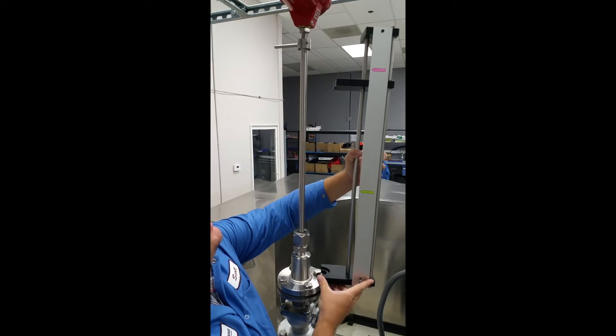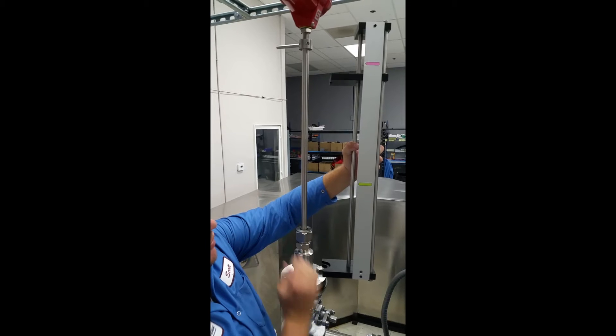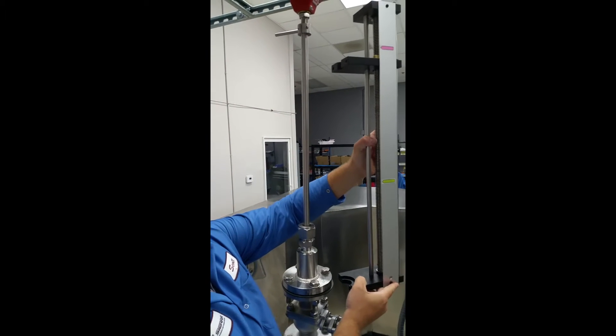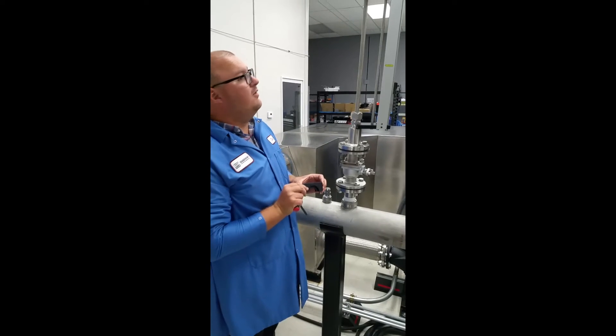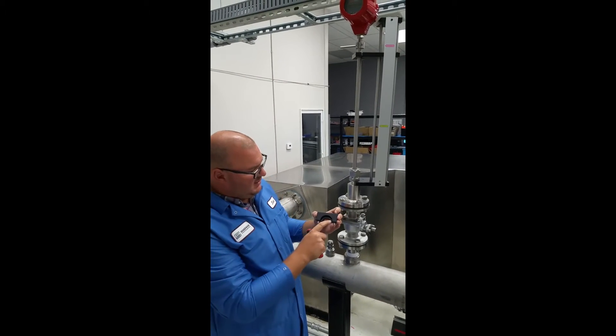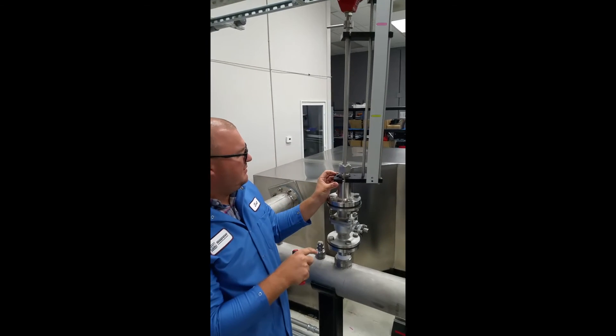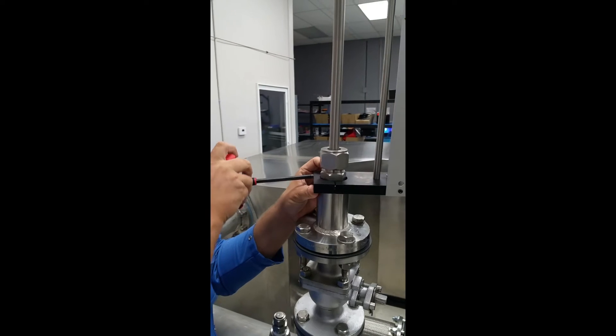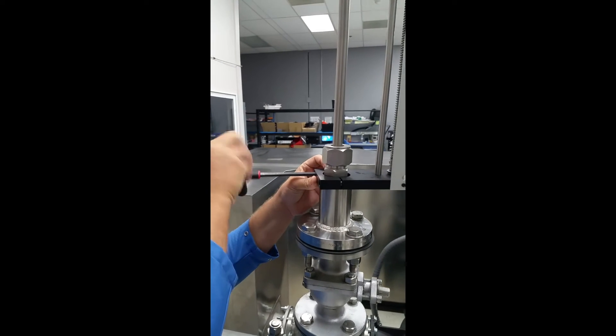The retractor is secured to the process connection and probe with these two brackets. Each one is uniquely machined so that it will only fit in one way. I've already just hand tightened the top bracket here. I'm going to install the bottom one. It has the same shelf that fits into the process connection like so. And it's important to leave the top loose for now because I'm going to have to index it in a second.